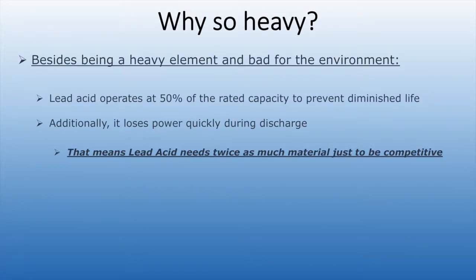There are multiple reasons why lead acid is so heavy, besides being a heavy element and bad for the environment. Lead acid operates at 50% of its rated capacity to prevent a diminished life. And by diminished life, what we mean is that if you try to 100% discharge lead acid and have a lot of cycles like we discussed before, you can't do that with lead acid. So lead acid actually uses twice as much material, so you can discharge it not as deeply and still get sufficient cycles. That creates a lot of extra weight.